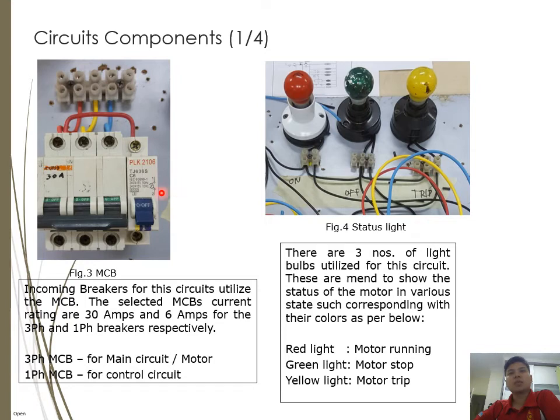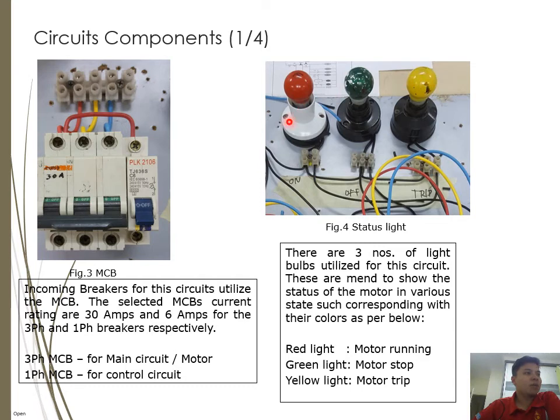The circuit breaker is the incoming breaker for this circuit. The selected MCB current ratings are 30 amperes for the three-phase breaker (for the main/power circuit) and 6 amperes for the single-phase breaker (for the control circuit). There are three light bulbs used to show the motor status: a red light for motor running, a green light for motor stopped, and a yellow light for motor trip.